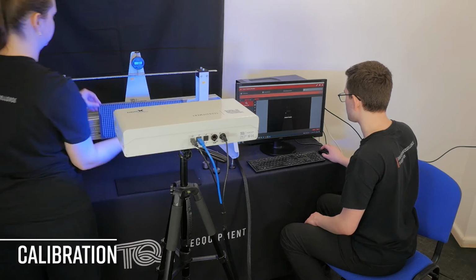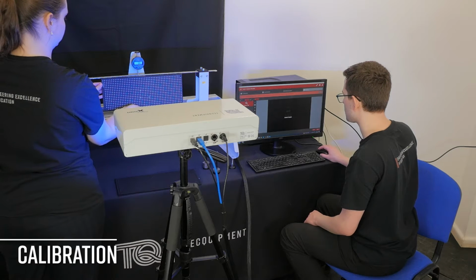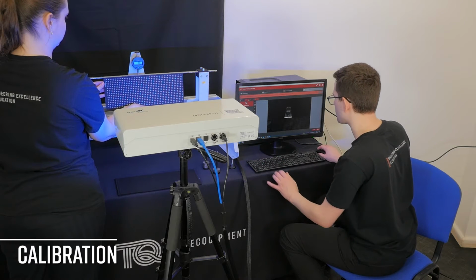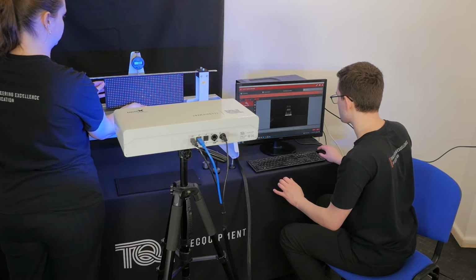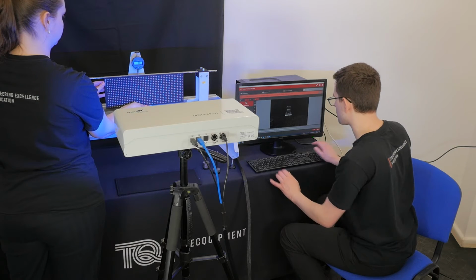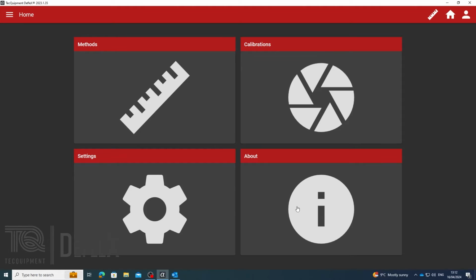Calibrating the system is essential to be able to measure anything. Calibration tells the camera the scale of the specimen, the distance to the specimen, and the specimen's orientation and positioning. The software reads the dotted pattern from the grid and calculates the distance between each point in pixels. With the real distance set by the user, the grid unit distance, the system can then calculate a pixel to millimeter ratio. On to performing a grid calibration.